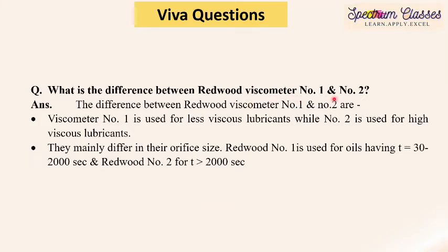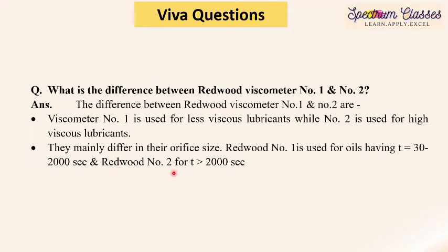The next question: what is the difference between Redwood Viscometer Number One and Number Two? They mainly differ in their orifice size — the nozzle at the bottom of the cylindrical vessel. Viscometer Number One is used for less viscous lubricating oils while Number Two is used for highly viscous oils; hence Number One has a smaller orifice and Number Two has a bigger one. Oils that require 30 to 2000 seconds to flow use Number One, while oils requiring more than 2000 seconds use Number Two.